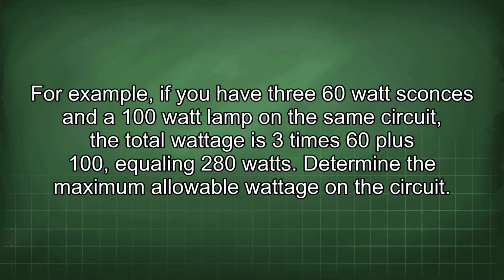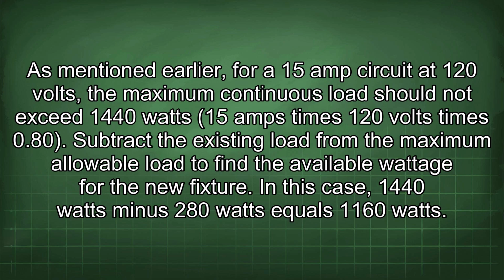Determine the maximum allowable wattage on the circuit. As mentioned earlier, for a 15 amp circuit at 120 volts, the maximum continuous load should not exceed 1440 watts. 15 amps times 120 volts times 0.80. Subtract the existing load from the maximum allowable load to find the available wattage for the new fixture. In this case, 1440 watts minus 280 watts equals 1160 watts.